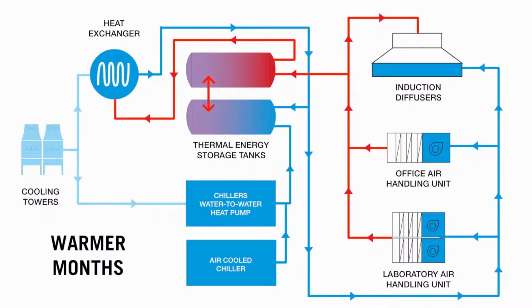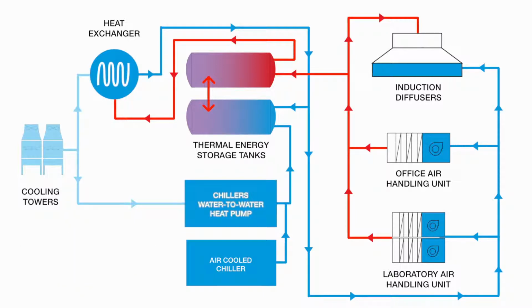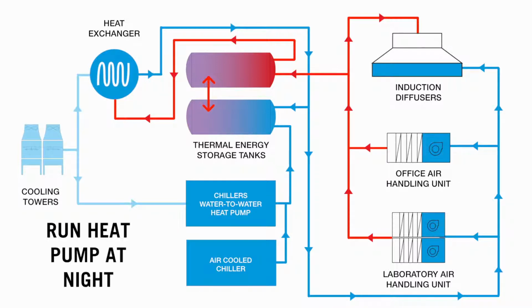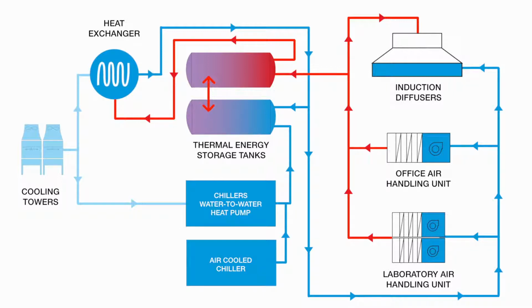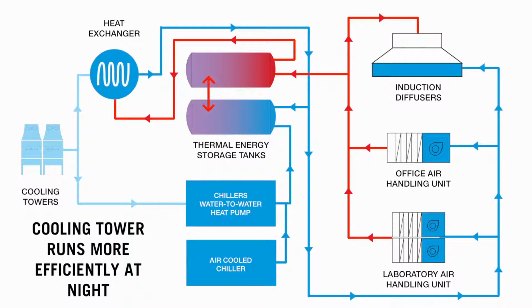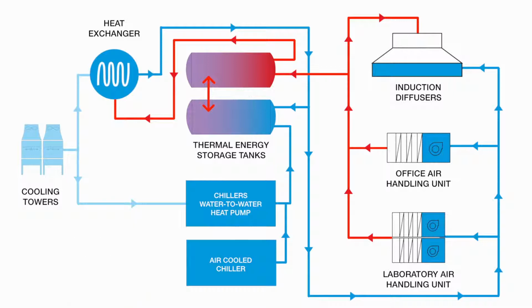In the warmer months, we have a water-to-water heat pump set up to be able to make the chilled water. And we run that water-to-water heat pump typically at night to make chilled water in the thermal storage tanks. And there's two reasons that we do that. One is at night, the cooling tower, where we reject the heat, runs more efficiently. And then also electricity is cheaper at night. So we get a lower cost of electricity and more efficient system if we make the chilled water at night. We fill up the chilled water tanks during the evening, and then during the day we're using that.